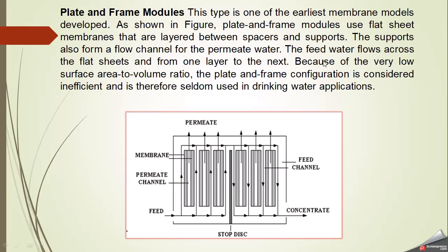So the feed water flows across the flat sheets and from one layer to the next. These are the different layers. If we need more water cleaning, we prepare a bigger size of this plate and frame module. Because of the very low surface area to volume ratio in this module, the plate and frame configuration is considered inefficient, and it is therefore seldom used nowadays in RO drinking water applications.